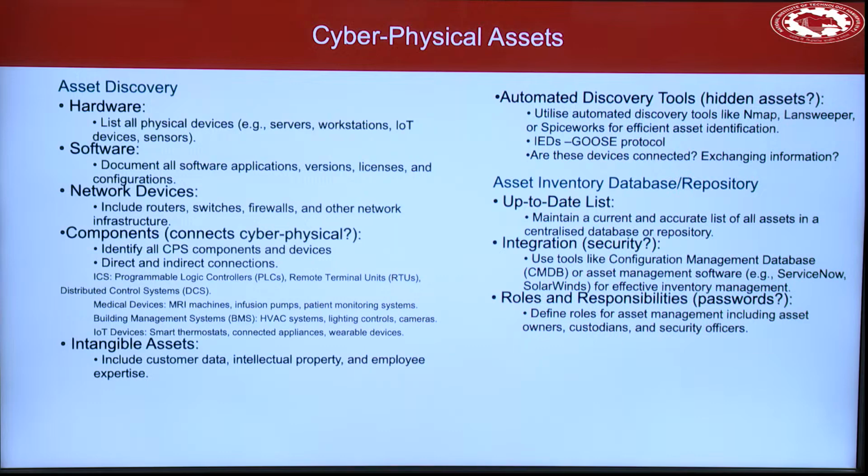IEDs use a protocol called GOOSE, which is the generic object oriented substation event protocol. This protocol does not require an IP address, so it communicates between IEDs directly. So, there might be some IEDs which are not connected to the network, and then your network scanning will not detect them.